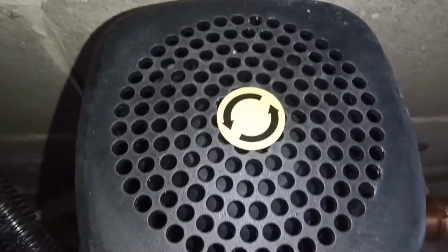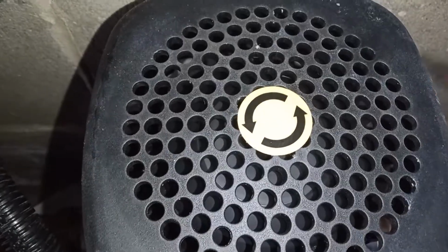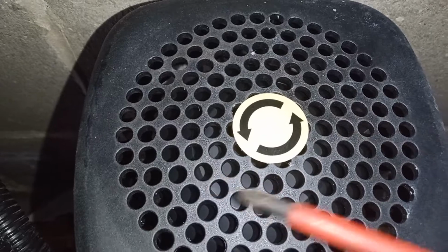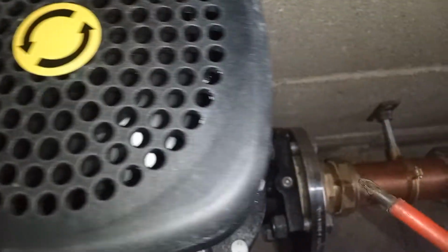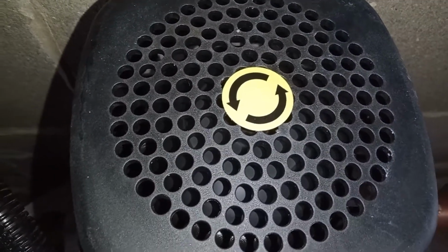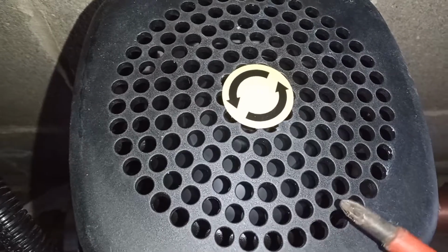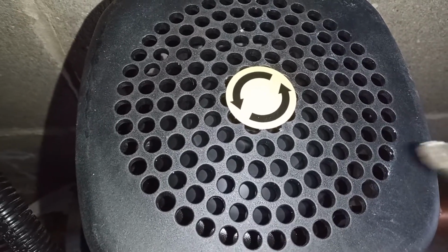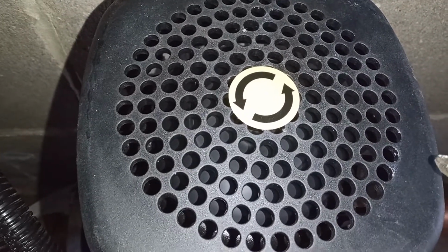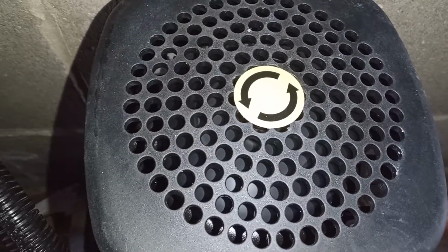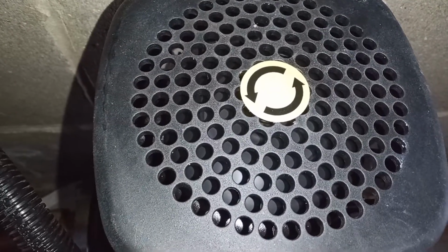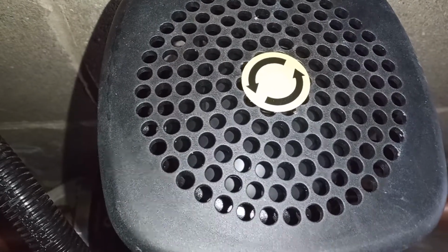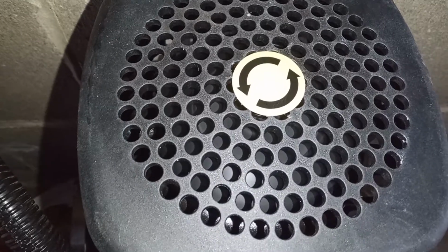So it looks as though we found the problem. The pump was not circulating in the correct direction, it was circulating clockwise. So what that did is that had the pump sending the hot water back towards the water heater. So we were depending on gravity, so only people on the lower floors would receive good flow rates of hot water and people on the top floor would receive poor flow rates. They still had hot water, but people on the top floor didn't have quite the flow rates they needed to receive.